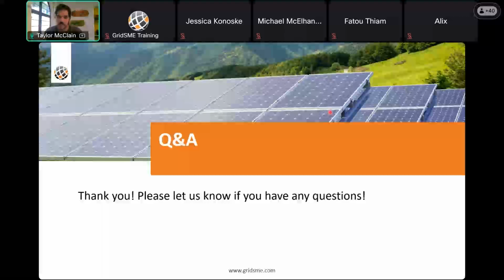And they will start benchmarking those and tuning the dynamic model that they have until it matches what the facility is actually doing in the real world. And so this is done consistently throughout the life cycle of a project to make sure that the dynamic models that the ISOs and PTOs have on hand are aligned with how the generators actually function.